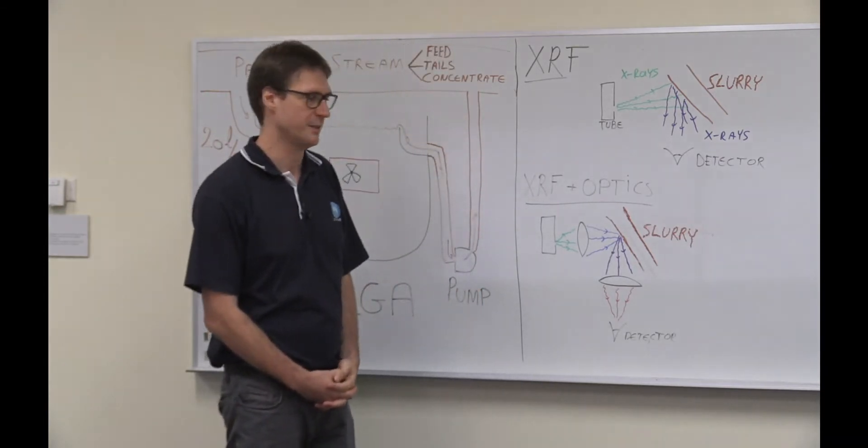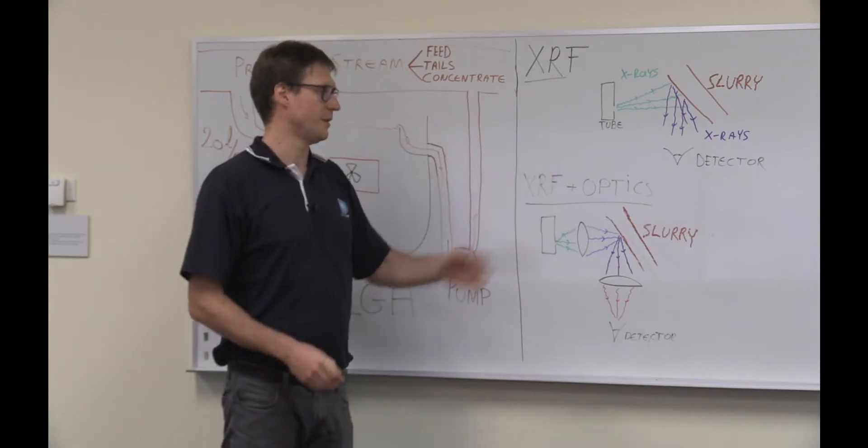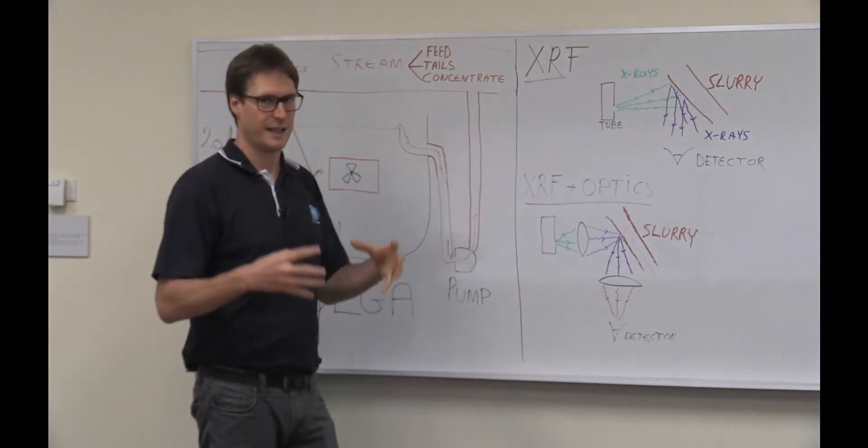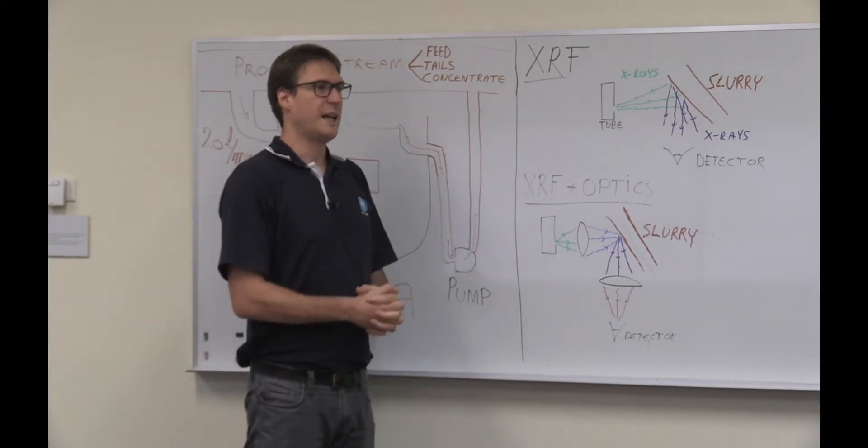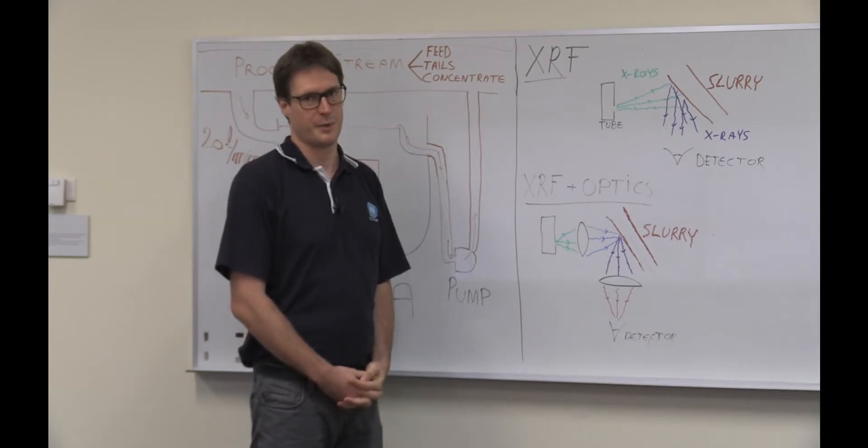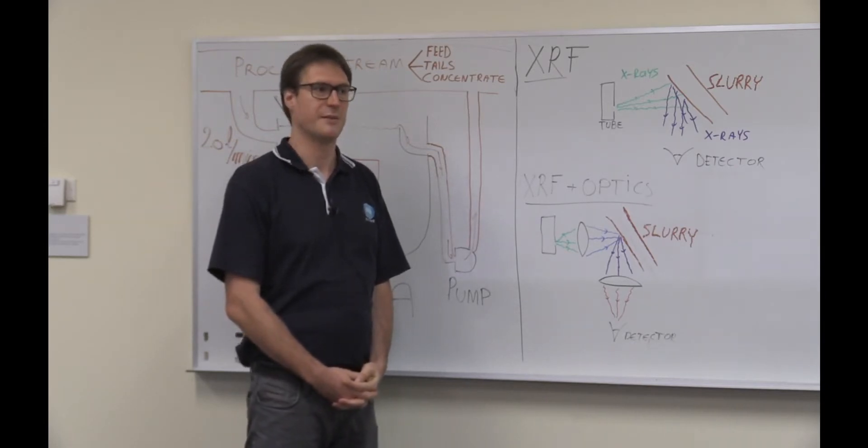So how do we push down the detection limit? Well, we do this by the usage of X-ray optics. An X-ray optic, in our case, is a crystal, and it works the same way a colored magnifying lens works for light, but then for X-rays.